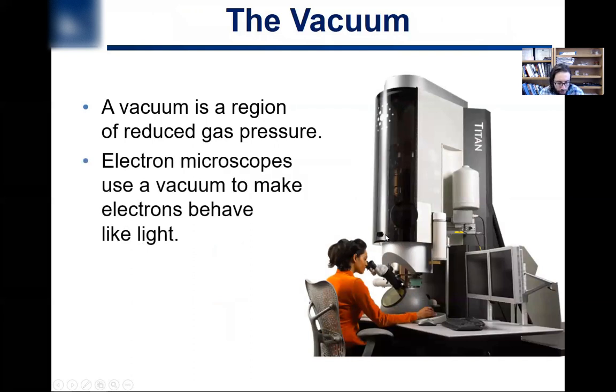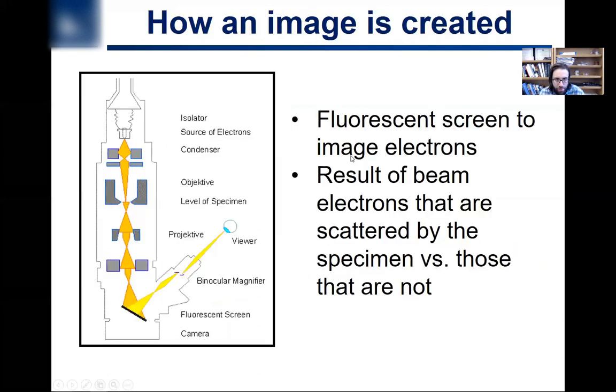And then part of what makes this thing so expensive is that the whole instrument is under high vacuum conditions. And so there's a series of vacuum pumps that bring it down to the correct pressure. And you need this because you don't want your high energy electrons bouncing into air molecules and ionizing air. Then the electrons aren't going to be able to be used in this microscope fashion.